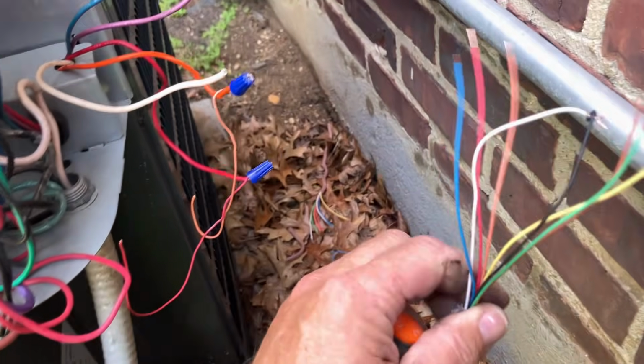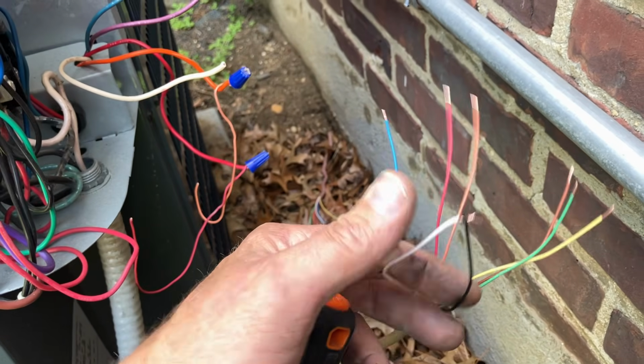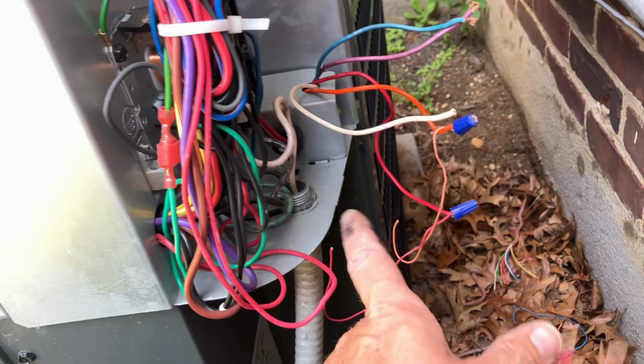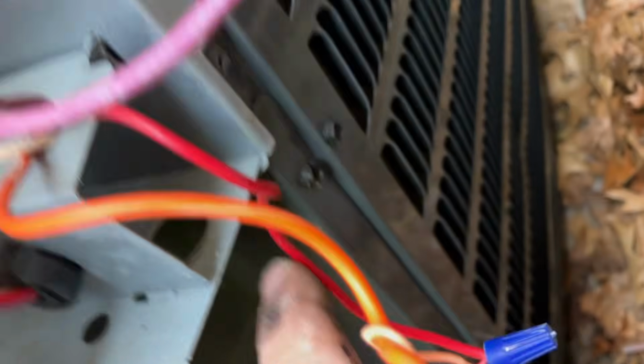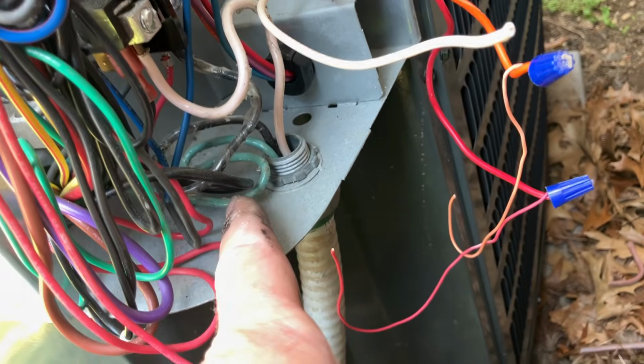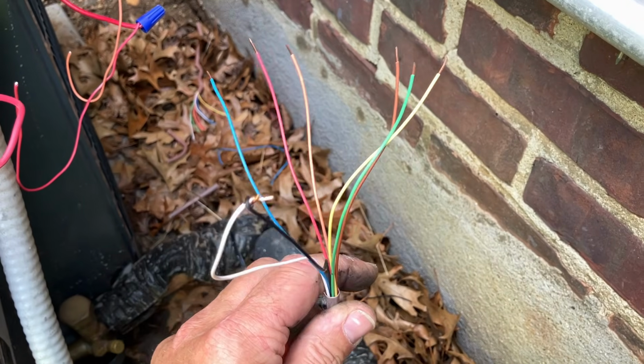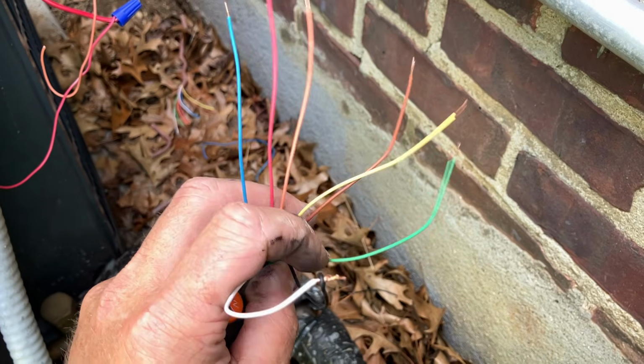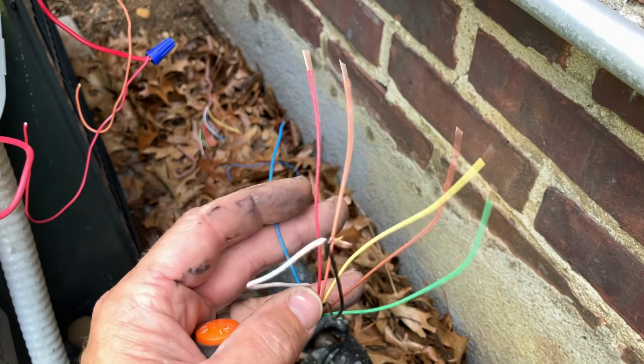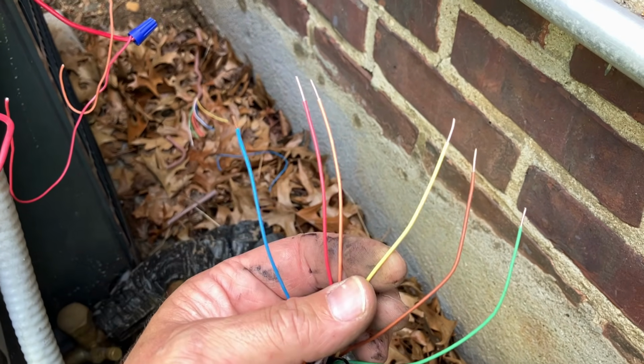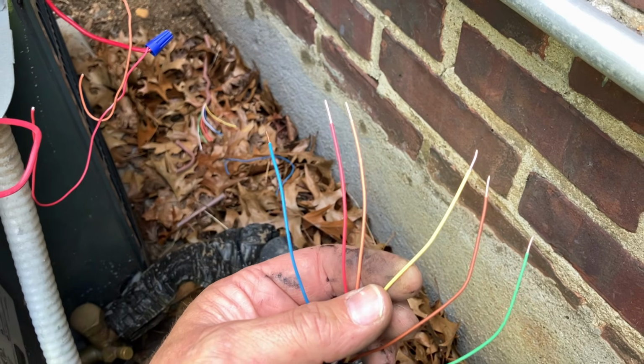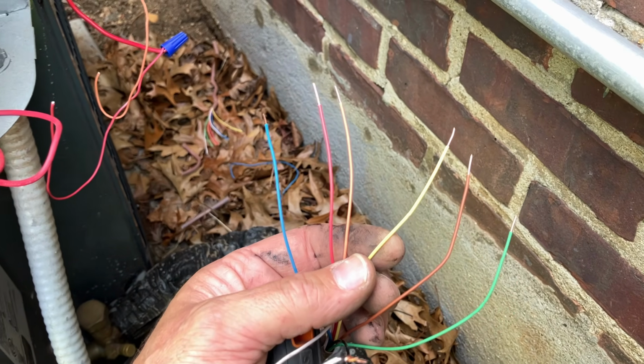So I pulled out my low voltage control wiring from that little hole. Instead of going there, they used that little hole and wrapped it around the line voltage for whatever reason. So upstairs at the air handler, I disconnected the wiring and twisted the blue and yellow wires together, then used my voltmeter to check for continuity, and I had none.